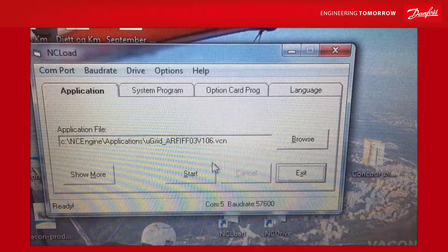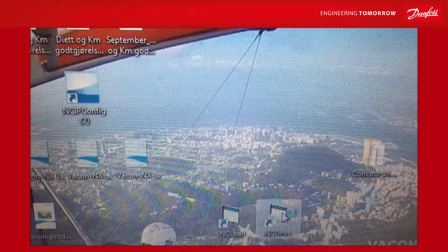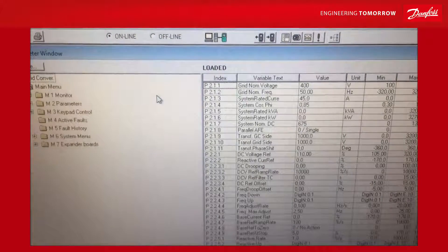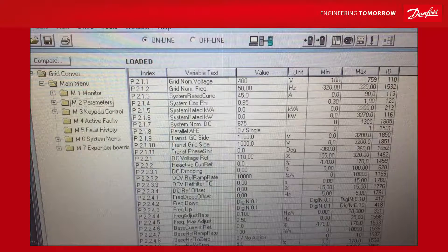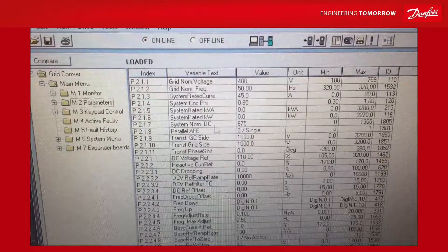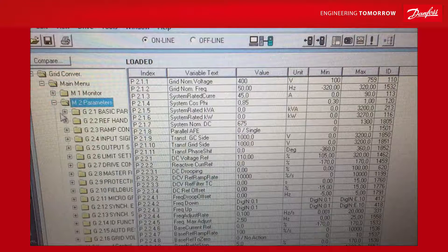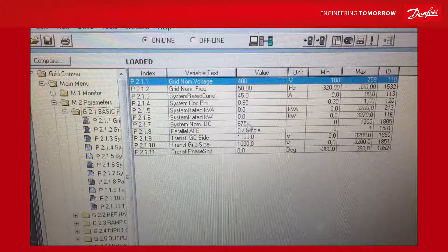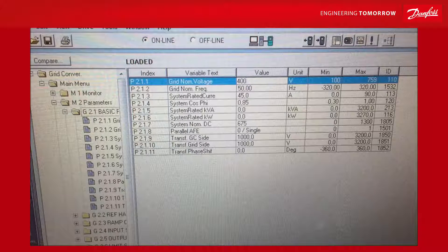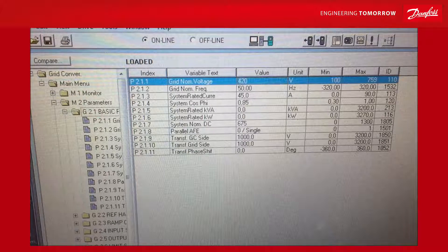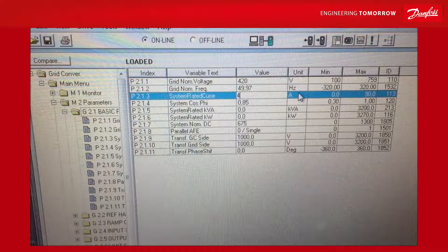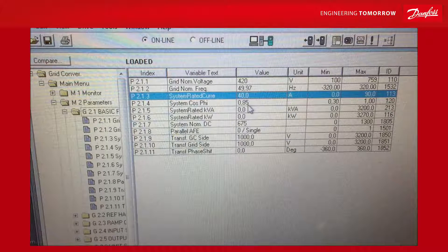Now that the application is downloaded, we open NC Drive, which will have only the default parameters. This is the parameter list — all parameters in one big list. To differentiate a little better we can select a chapter, for example basic parameters. Here we see that the grid nominals and frequency are default parameters. We know that we are using 420 volts, and the frequency should be 49.97. System rated current is 40 amps, and the power factor is correct.